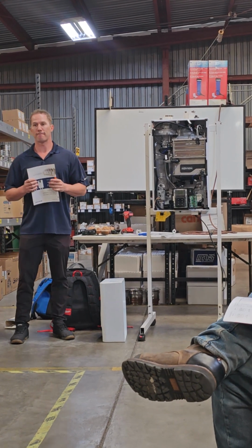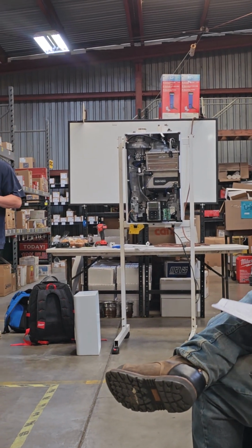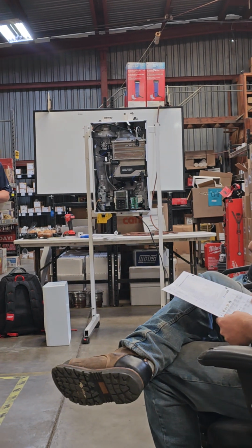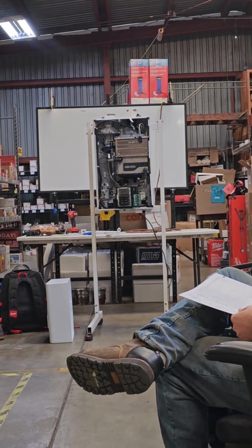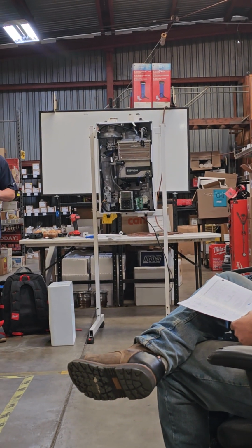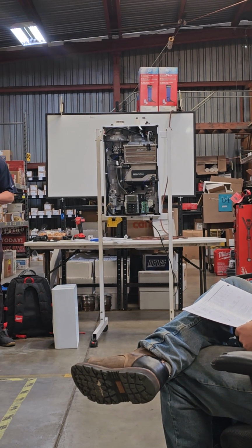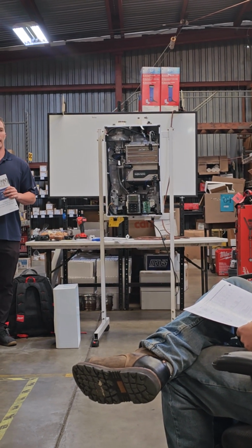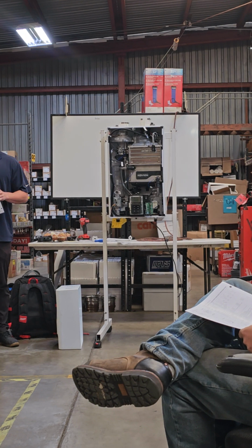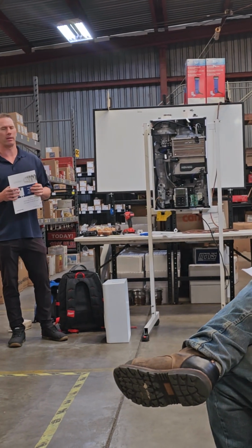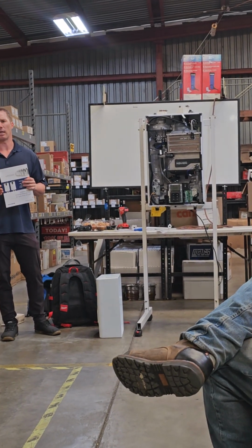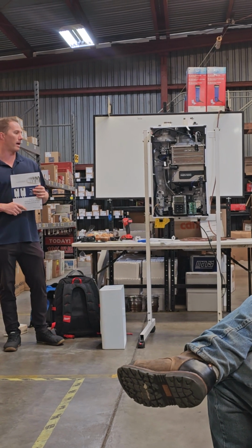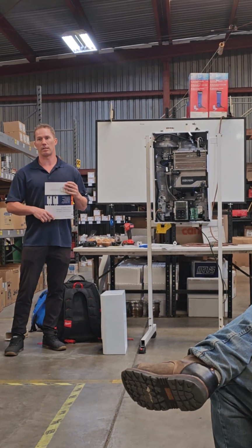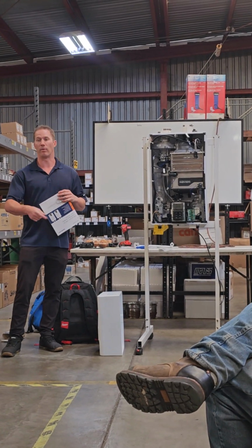What's the minimum gas flow? So for natural gas, it's 3.5 to, I think, 10 inches of water column, and propane is 8 to 13. Maybe 13.5, but yeah, I think 8 to 13. And that is dynamic, not static. So that's dynamic when they're running about 4 gallons per minute.